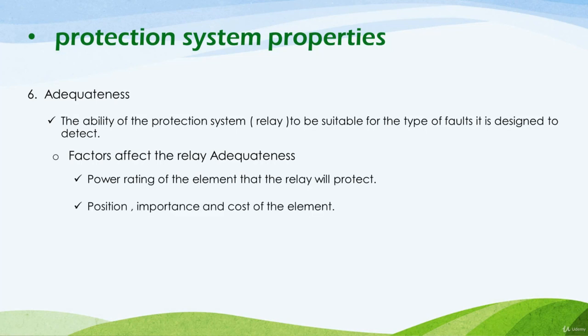And also the cost of the protected element, and this is because when the element we need to protect has a larger cost, this means it's an important and sensitive element, so we need a more efficient and reliable protection system to protect it. While if the protected element was a less important one, or it cost us less, we don't need a very reliable protection system to protect it, and it will be sufficient to use an ordinary protection system as the protected element itself is not an important one.